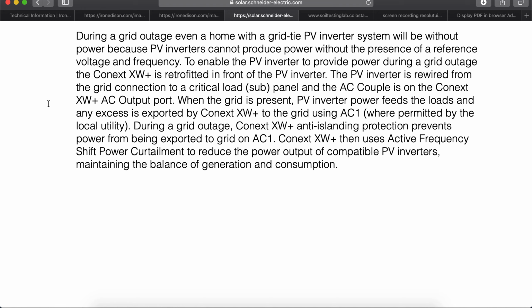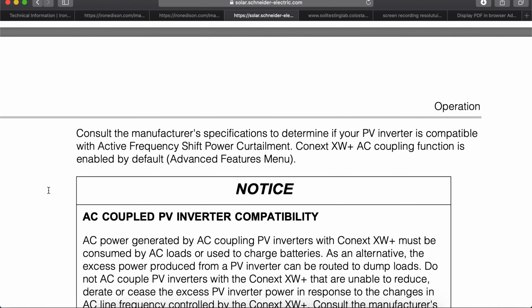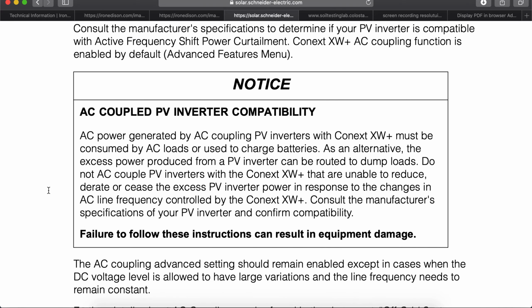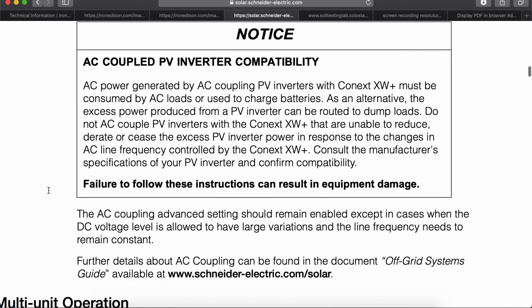During a grid outage, the Conext XW Plus anti-islanding protection prevents power from being exported to the grid on AC1. The Conext XW Plus then uses active frequency shift power curtailment to reduce the power output of compatible PV inverters, maintaining the balance of generation and consumption. Got to make sure those PV inverters are compatible.